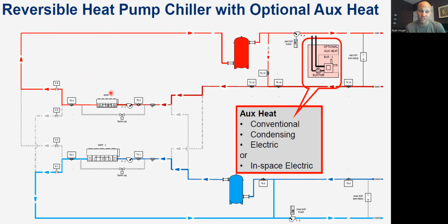Instead of having 2 chillers here, this heating chiller can become my other cooling chiller, right? And these valves can open, and now basically this water loop is off, circulators are off. I don't send any hot water out to the building, but the chilled water can flow through this machine, and it can go up the gray line, and flow through the other chiller with the reversing valve flipped to cooling mode and come back in. So now I can have these 2 chillers working in parallel for cooling mode, and then come heating season, it can flip, and it can be back to the opposite.